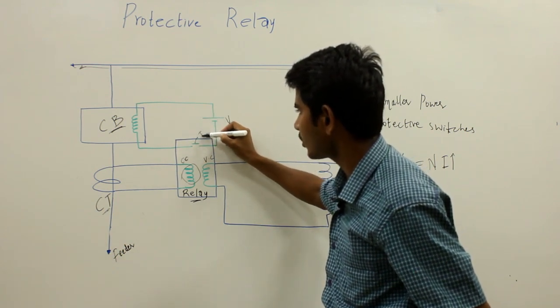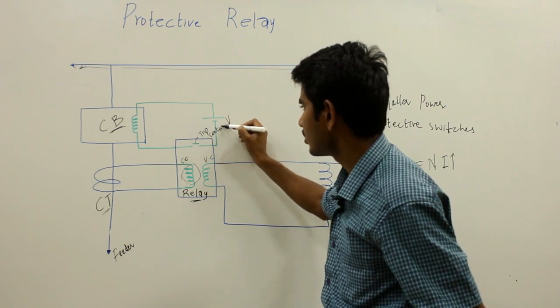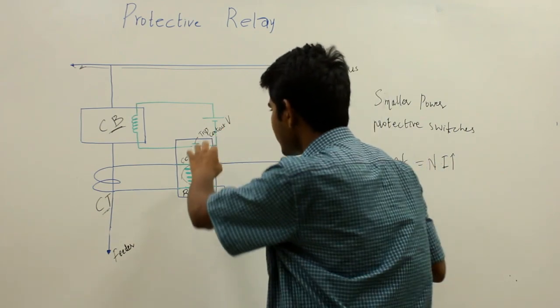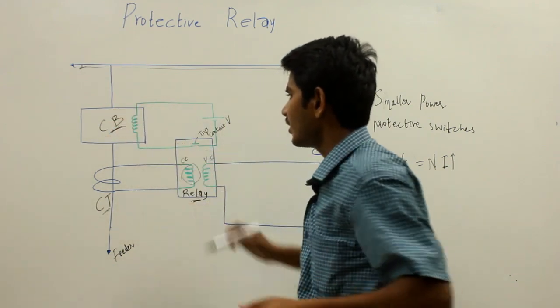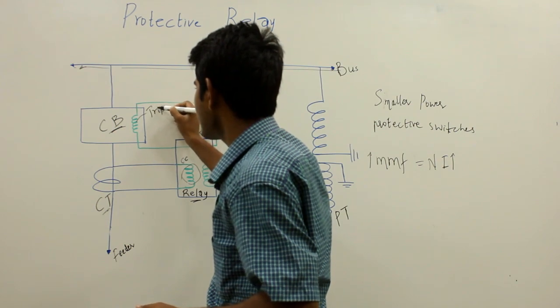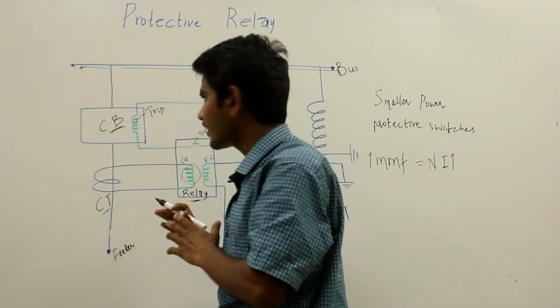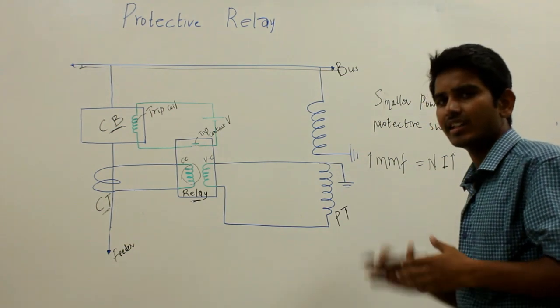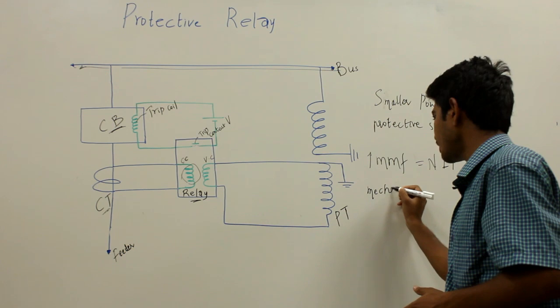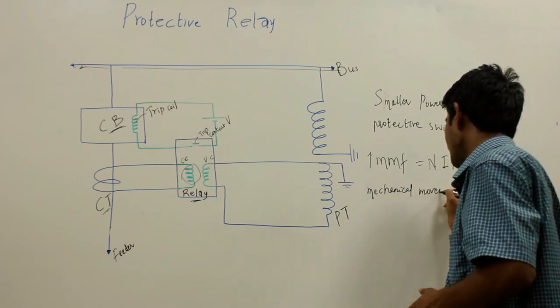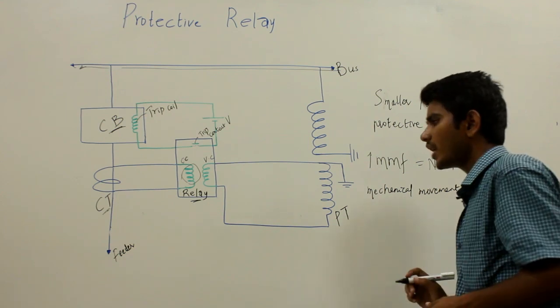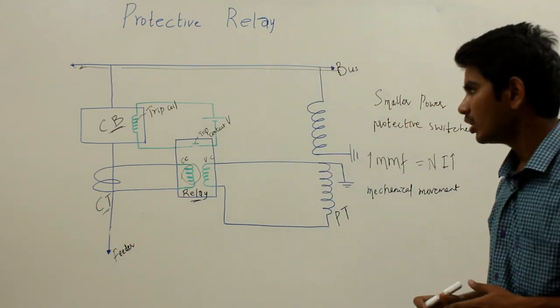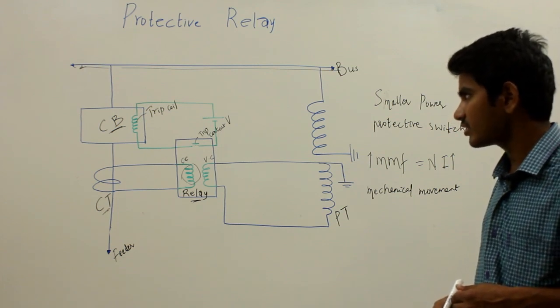This trip contact gets closed as the MMF of the coil increases, and when it closes the DC trip coil circuit is completed. Once the circuit gets completed, the trip coil gets energized. This trip coil, after getting energized, initiates the mechanical movement of the tripping mechanism to isolate the faulty portion, and ultimately the circuit breaker is tripped to isolate the fault. This is basically how the faulty portion is isolated in a power system using the protective relay.